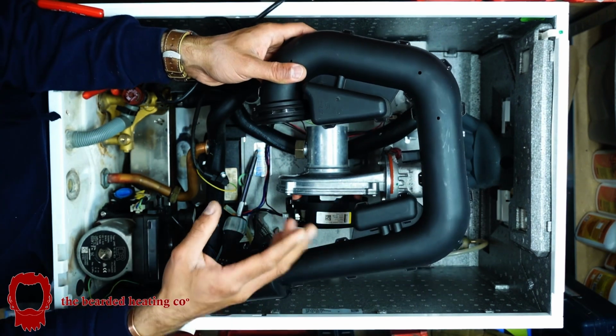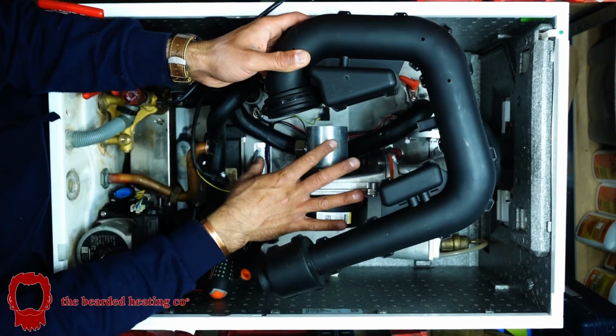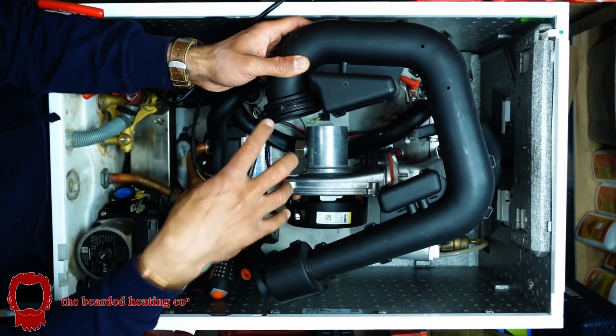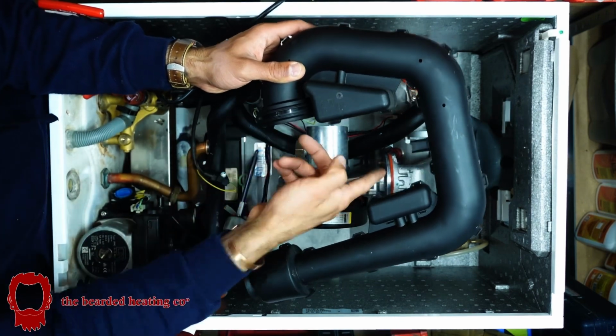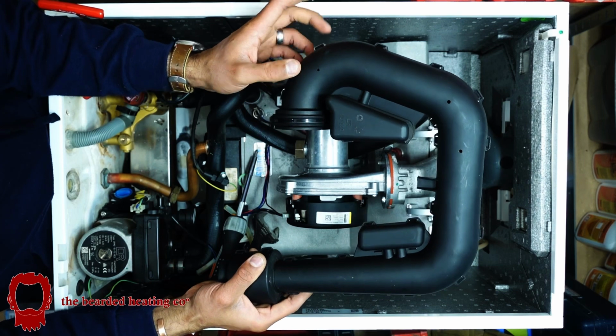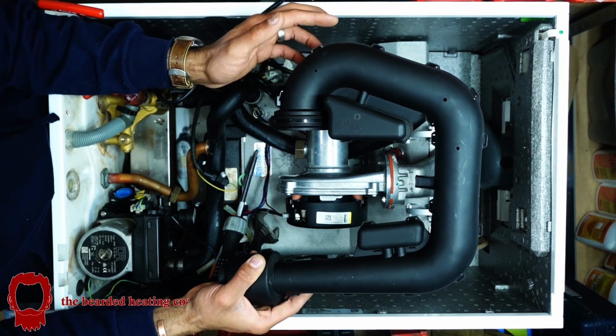I forgot the word for it - yeah, pre-mix. That's what a condensing boiler is, that it mixes the air and the gas prior to burning. Hence why you have to always set the CO2 on combustion on high and low to make sure that's all burning correctly. But that's the air intake out of the way, and now we're at the fan.